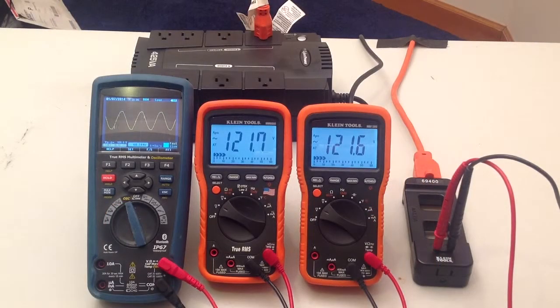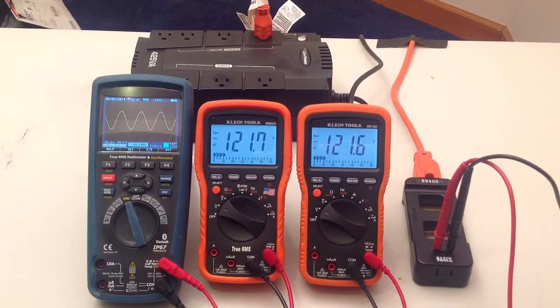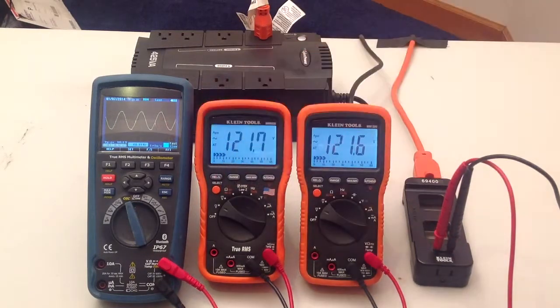A true RMS multimeter gives you an accurate representation of the amount of energy in your AC waveform. It actually takes measurements throughout this and calculates the total energy, where a non-true RMS meter just looks at the peak to peak level and averages out what it believes the energy is.